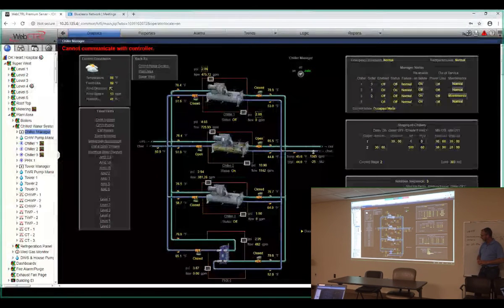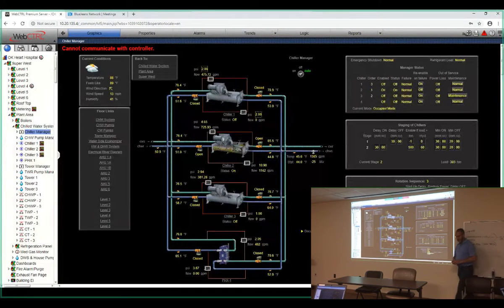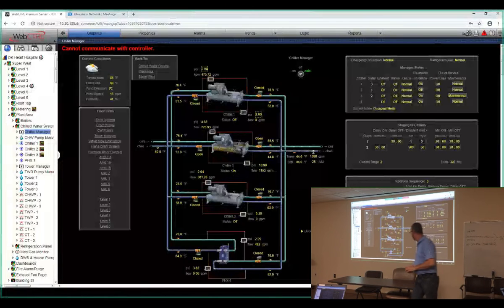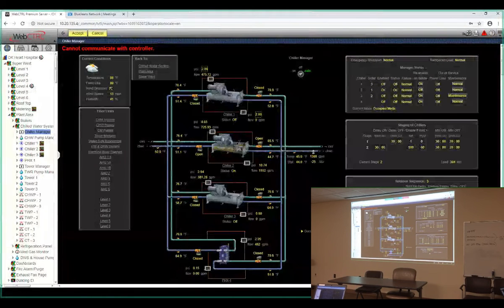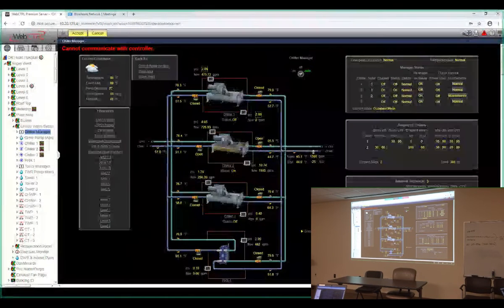So clearly, obviously in this rotation sequence, chiller 1 would start before chiller 3 would go off, right? If there's only demand for one chiller? Correct. Yep, and that's this little section right here. Yeah, so that's this portion of startup delay and the delay off. We've got a startup delay and a delay off, and I've got a lot of timing built into the sequence to take care of that.